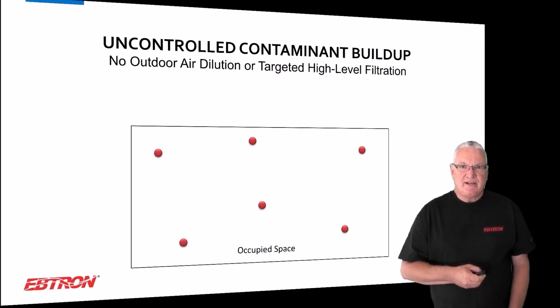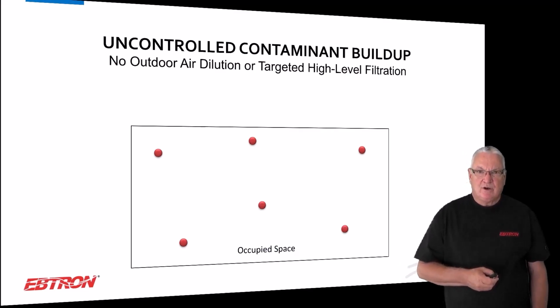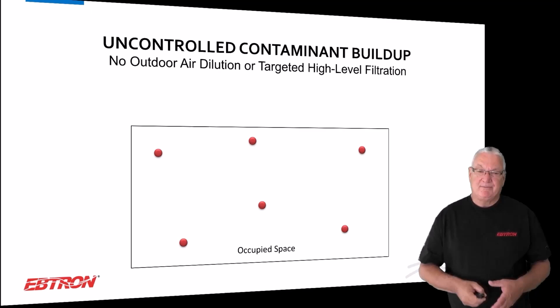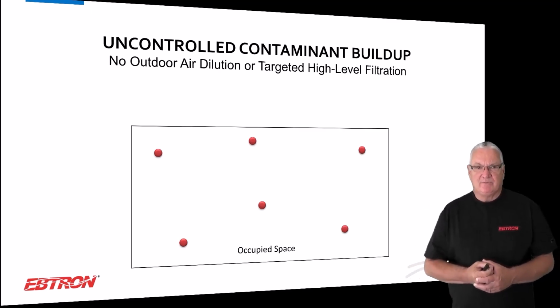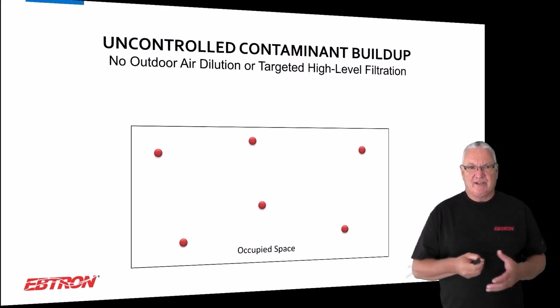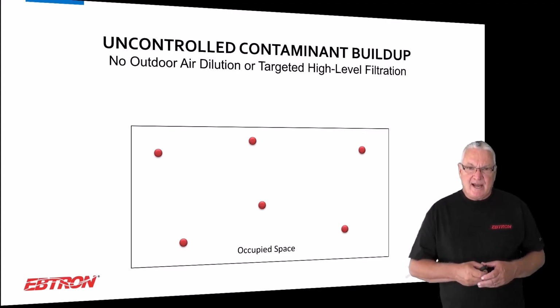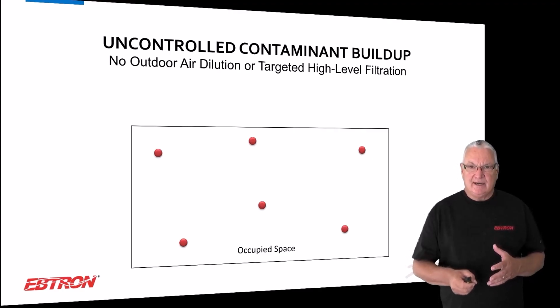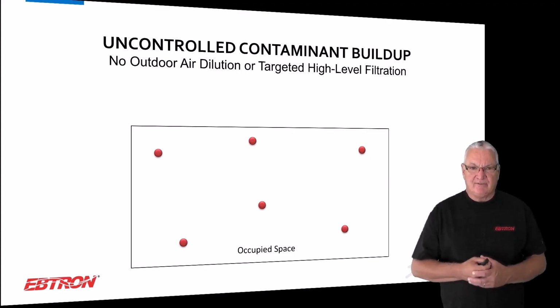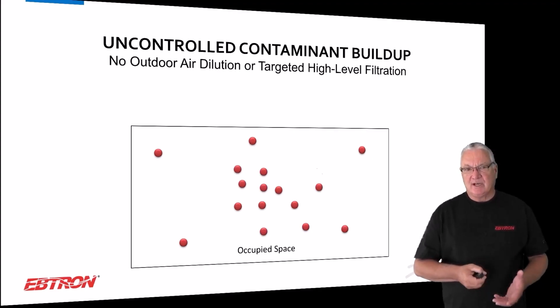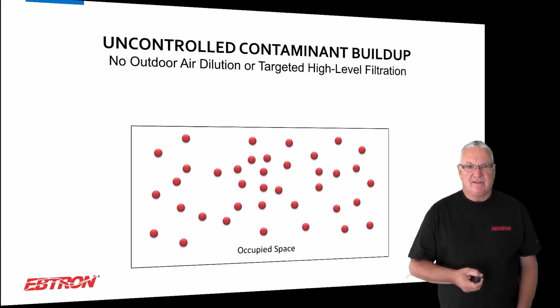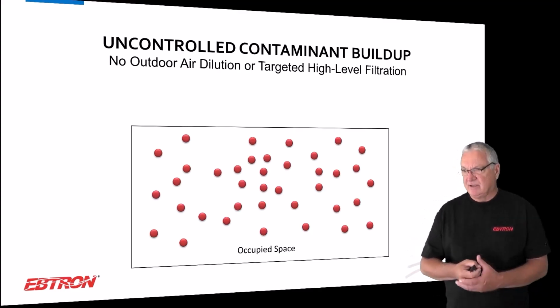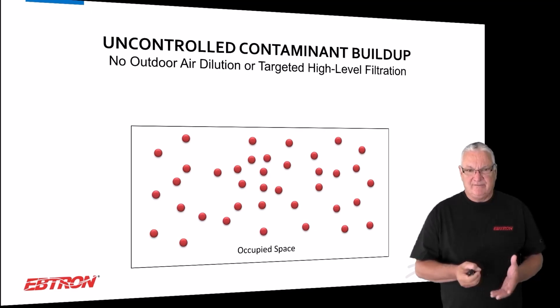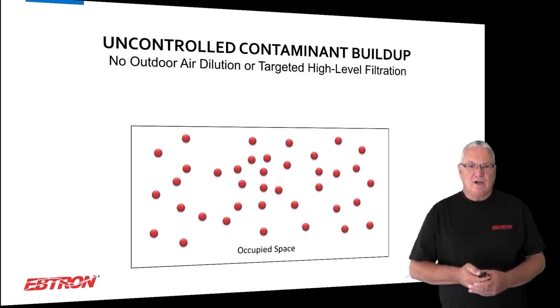Well, when it comes to air changes, what are we talking about? We're going to be talking about room air changes. I call them room air changes and outdoor air changes. Sometimes people call them different things, but how much air are we changing in the space? So if we don't have any outdoor air or any targeted high-level filtration, what is going to happen? Well, we're going to have the contaminants build up in the space. And even though we're talking healthcare, this could be just about anything. It doesn't have to be a healthcare facility; it could be any facility that you have. So what can we do about it?